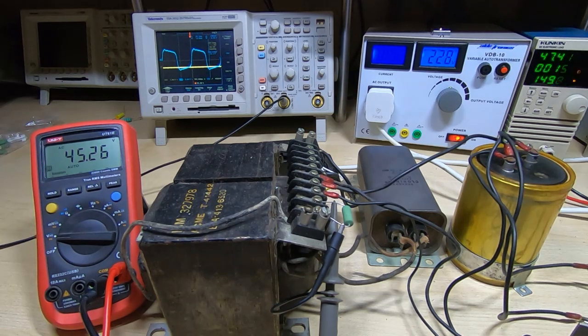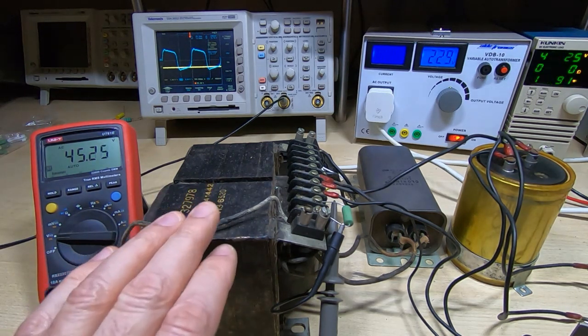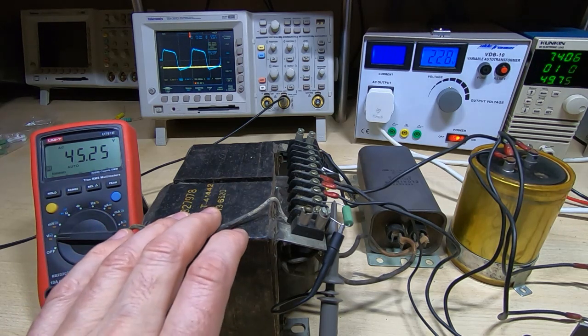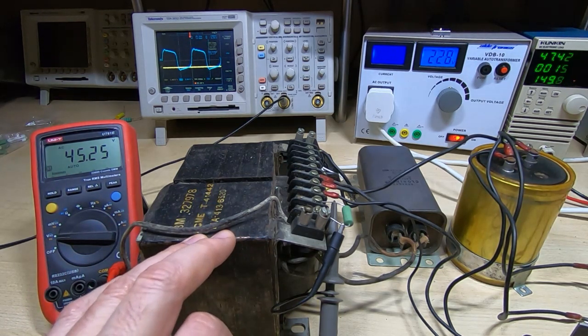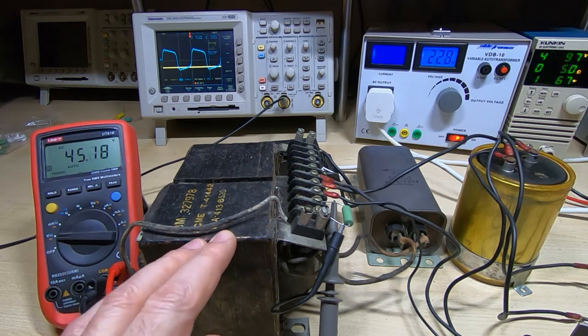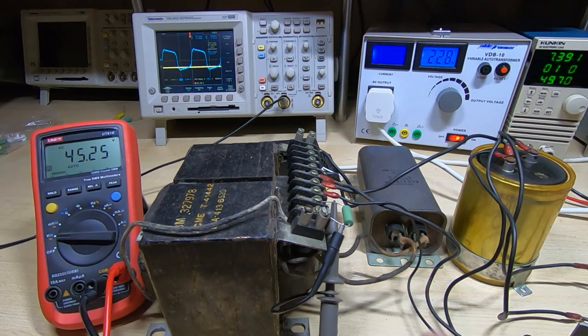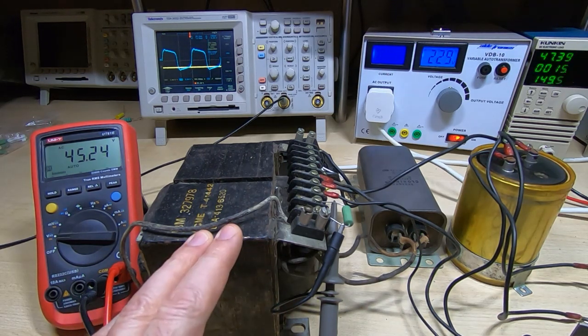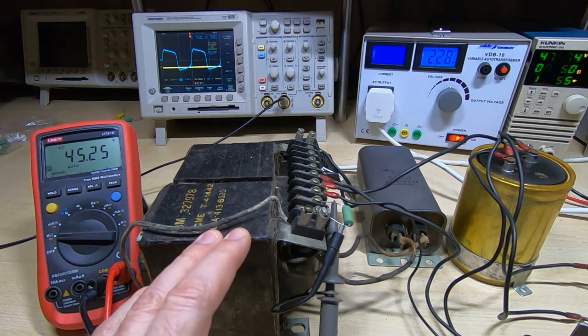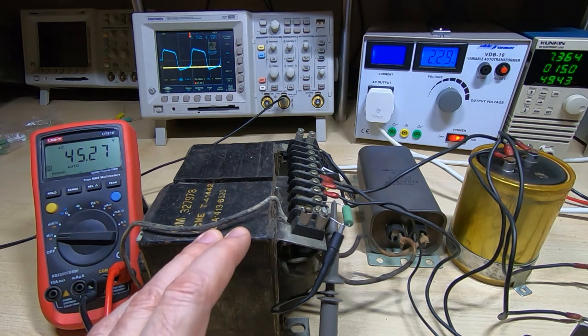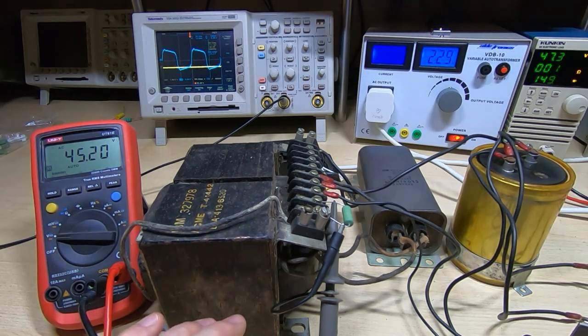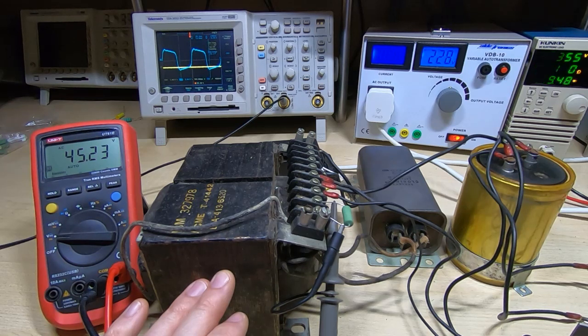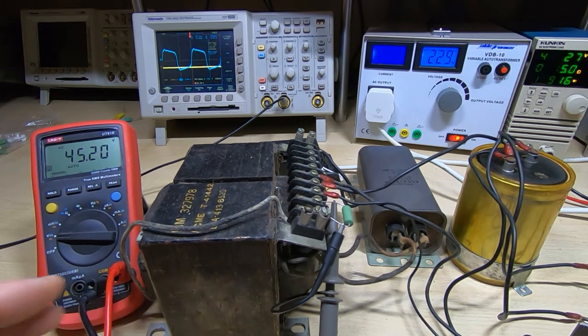Okay, well I hope that makes sense. As I say, just to recap, the transformer works by running the primary in the linear part of the flux curve. The secondary part of the transformer core is driven into saturation through the use of a resonant winding and capacitor circuit. That resonant circuit causes the secondary part of the core only to run into saturation. The two parts of the core, the primary and secondary, are partly isolated through the use of magnetic shunts, and that allows only the secondary part of the core to run into saturation.